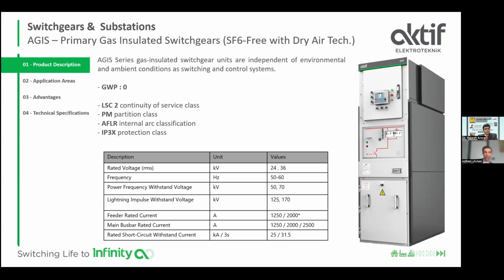According to IEC specifications: loss of service continuity LSC2, PM partitioning class, AFLR internal arc classification, IP3X protection class. The AGIS product has the 24 and 36 kilovolt voltage levels. Feeder rated current is 1250 amps and 2000 amps. 2000 amps will be published in the first quarter of 2025. Main busbar rated current 1250, 2000, 2500 amps available for now. Rated short circuit withstand current 25 kiloamps and 31.5 kiloamps with 3 seconds.